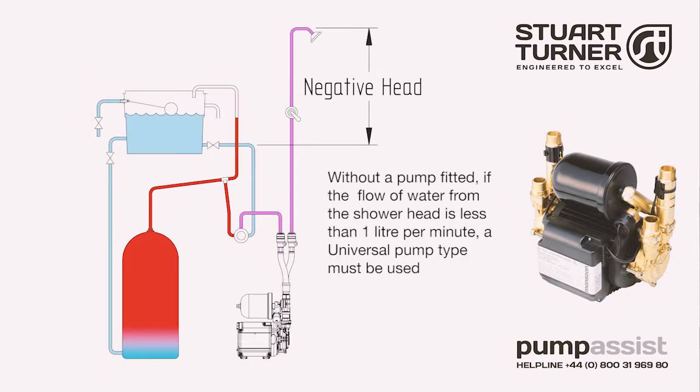In this situation the universal pump must be used. In addition to the flow switch, the universal pump also includes a pressure switch, and when an outlet is opened the pump is activated by the pressure switch and it continues to run using the flow switch until an outlet is closed.